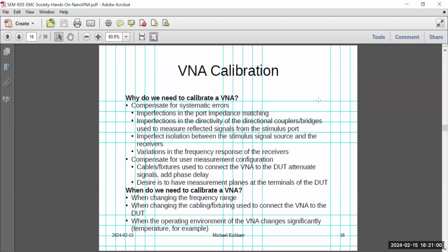And then as far as the user, this is like, okay, all the cables, the fixturing you've got to use to get the signal connected from your VNA to your DUT. The desire is that, in the VNA world, we talk about the measurement planes - that's the cross section of where the signal flows through, and you want that to be right at your DUT. If it's not, then what you're measuring isn't what's going on at the DUT.